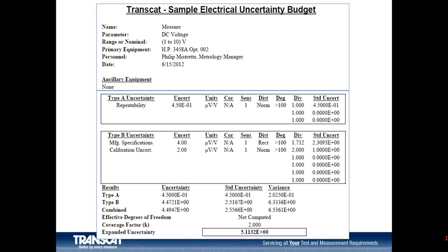In this case, those are separately listed items because the review of the manufacturer's specifications either did not include the calibration uncertainty, or the amount that was allowed for in there was not a good match to the uncertainty in the actual calibration of this tool.